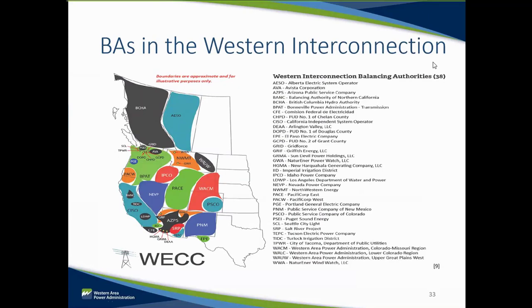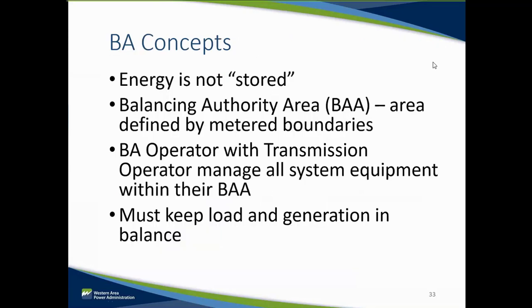Here is a WECC map showing the 38 BAs in the Western Interconnection. Since energy is not stored on the power grid, generation must be constantly adjusted to match the ever-changing load, and the balancing authority areas are what makes this work. All power system equipment located inside a balancing authority is the balancing authority area, and these balancing authorities are necessary to keep load and generation in balance.